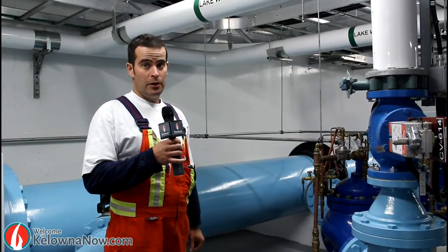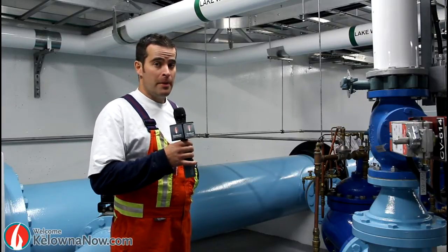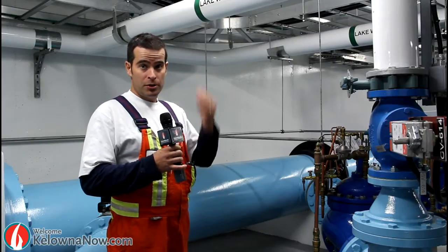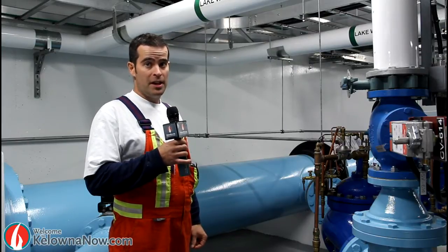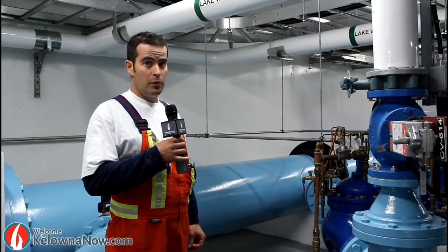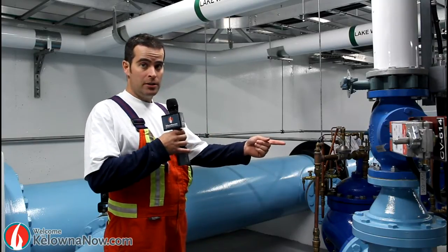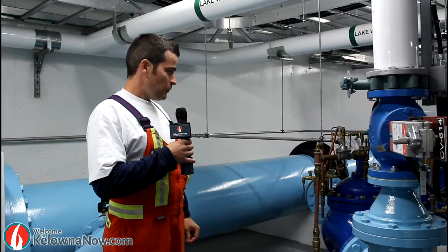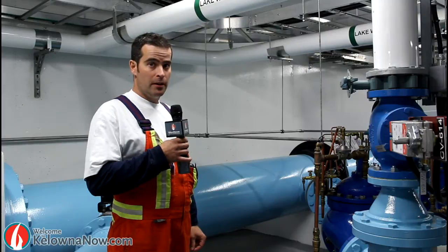In the event of a power failure, you have all this water that's being pumped up the hill, so you have an enormous amount of energy. During a power failure, these pumps will just automatically shut down abruptly, and that's going to cause a lot of water hammer coming back down. The idea of these surge anticipating valves is to take that water, redirect it, and kind of mild out the surge. That will dump the water into the lake caissons, which will go back out into the intake, minimizing surges during abrupt shutdowns of the pumps.